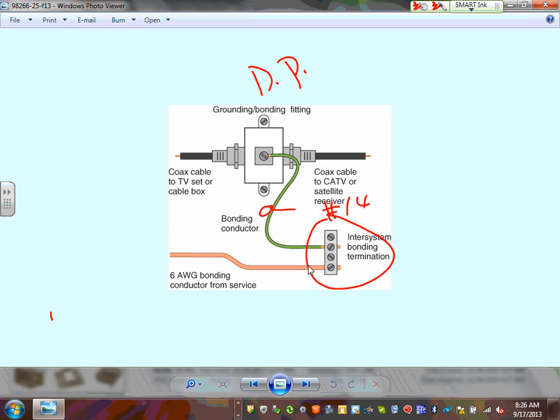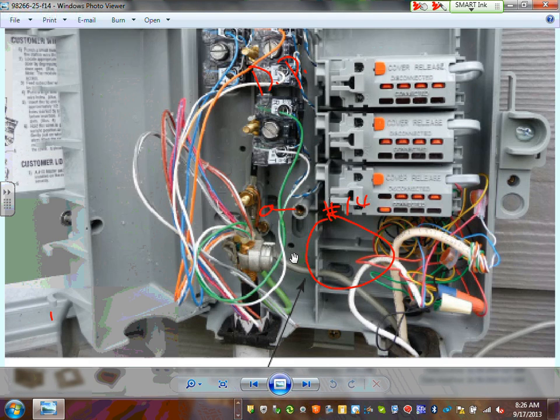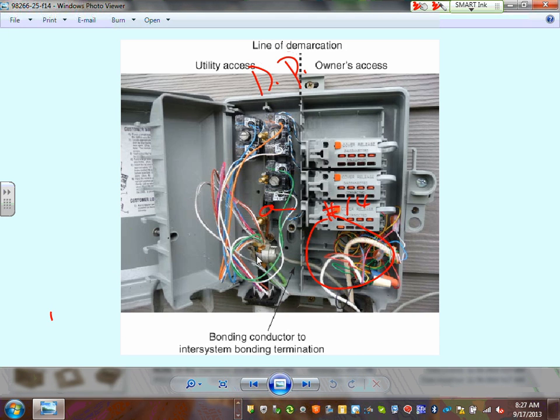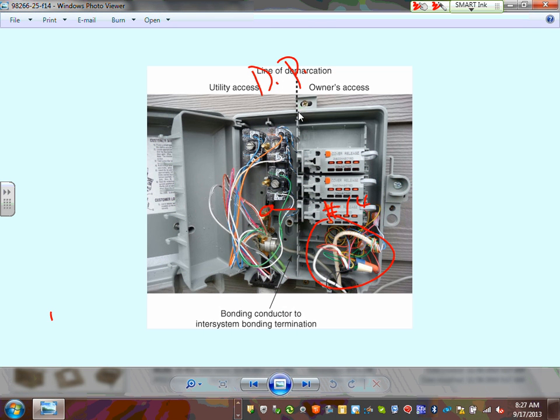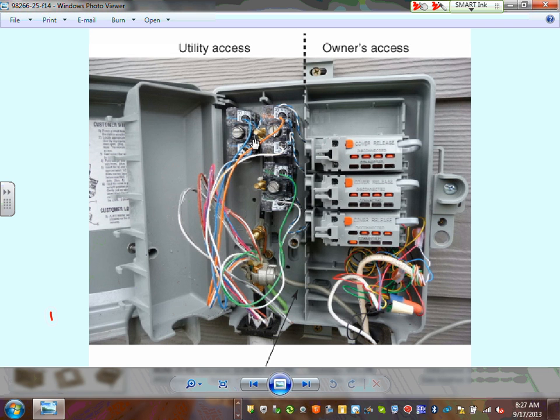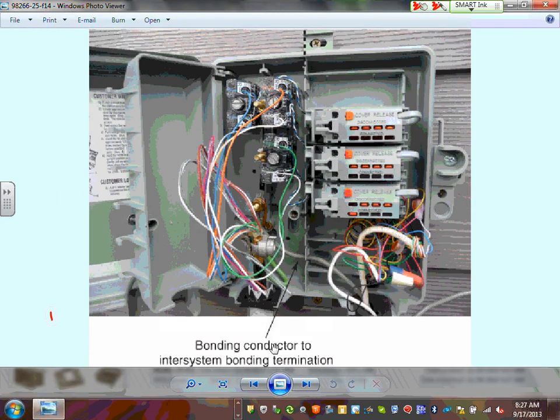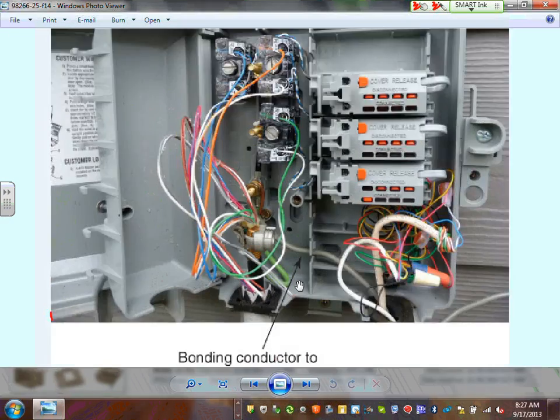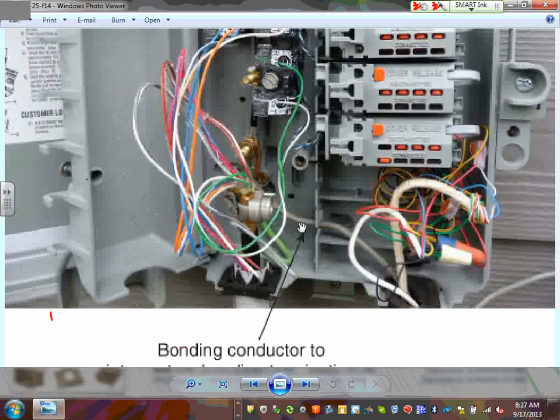You have to ground the shield for cable TV or phone lines if they have a shield. I don't know if you can see, but there's a box that sometimes gives you the line of demarcation for the low voltage - one side is for the utilities, the other side is for you. I believe this green line is where you're grounding, where you take your grounding bonding conductor. That gray conductor looks like it's my bonding conductor to the inter-system bonding jumper - not sure why they're using gray here.